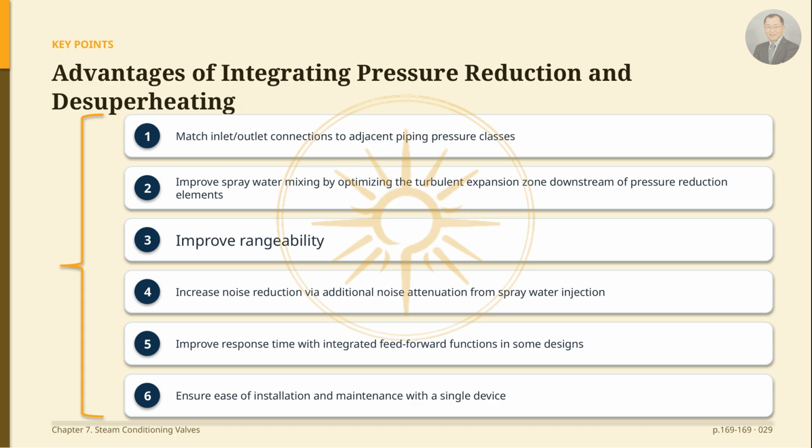spray water injection. In some designs, response time is improved thanks to an integrated feed-forward capability. Above all, the process is much simpler since only one device needs to be installed and serviced. There are several steam conditioning valve designs that leverage these advantages, and we will cover typical examples next.